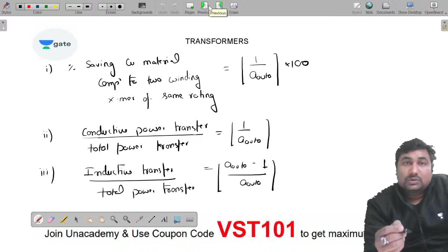Is it okay, Vinayak? In case you are going with the series subtractive polarity, there is a difference between series additive and series subtractive polarity. All these formulas are only valid for the series additive polarity. The formulas are not valid for the series subtractive polarity. We never use the subtractive polarity. The reason behind that is we are not getting the maximum kVA capacity. So it is better to go with the maximum kVA capacity.